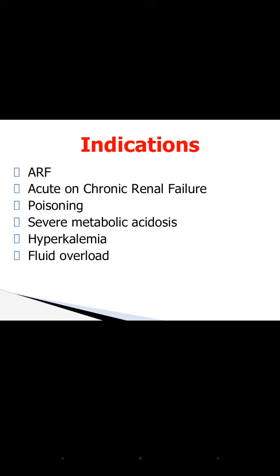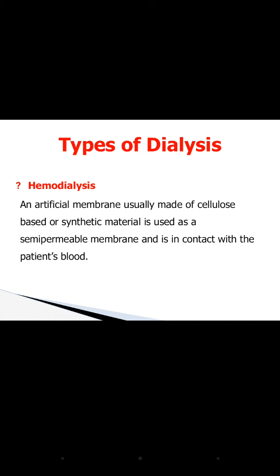It is a type of dialysis in which an artificial membrane is used, right? So in the hemodialysis machine we have a dialyzer, and this dialyzer is made up of cellulose or synthetic material, and this acts as a semi-permeable membrane. And why is it called hemodialysis? Because this machine is in contact with the patient's blood, that's why it is called hemodialysis.